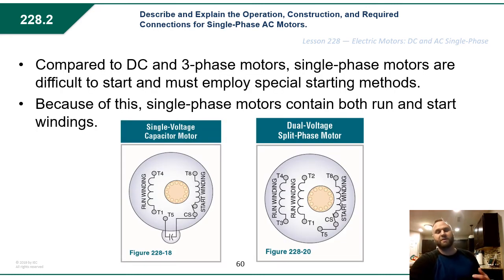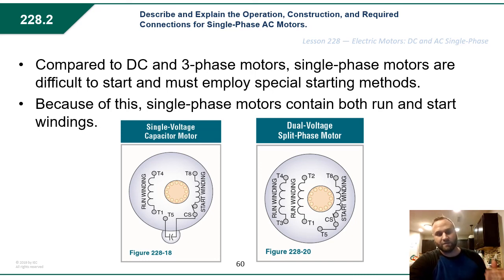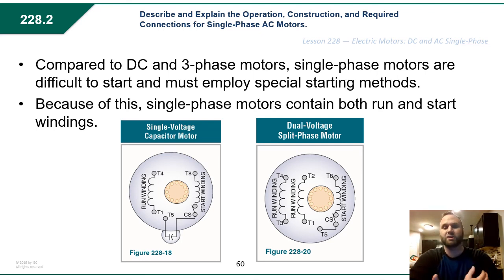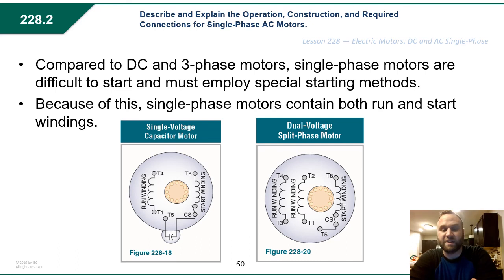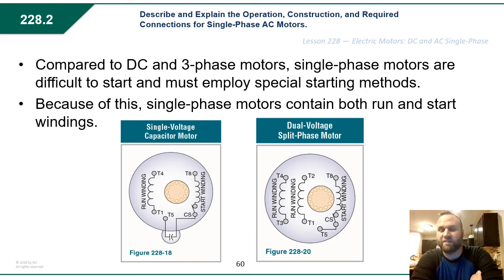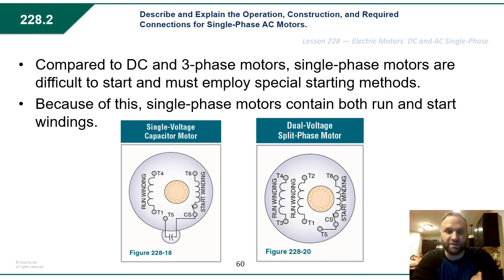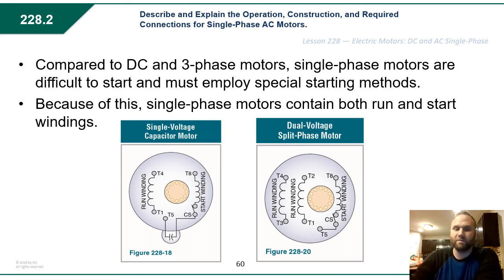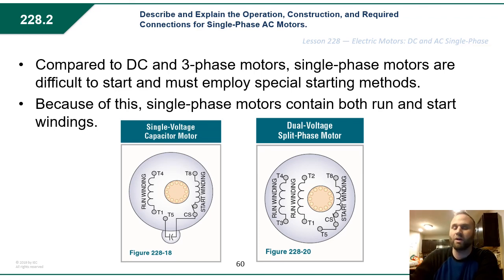Compared to DC motors and three-phase motors, single-phase motors are difficult to start and must employ different special starting methods. There are two fluctuating magnetic fields that try to cancel each other out, so in order to get the motor started, one of those fields needs to be canceled out through the start winding. Once the start winding is engaged and the motor starts to turn, even if the start winding is disengaged, the motor will continue to turn in the same direction. Single-phase motors contain both run and start windings — start windings to help start it, run windings to keep it going.